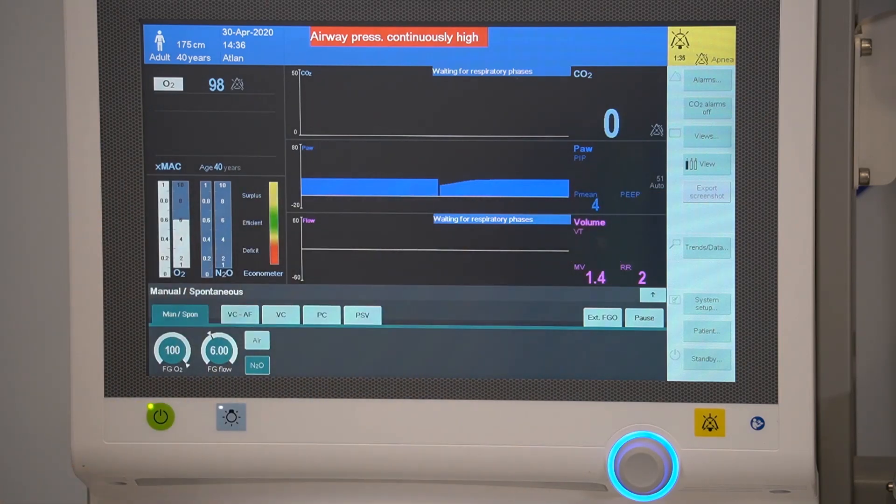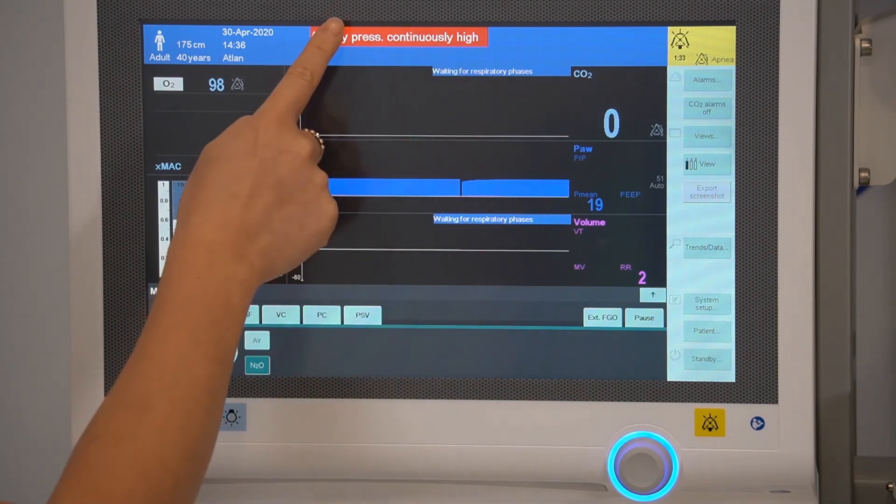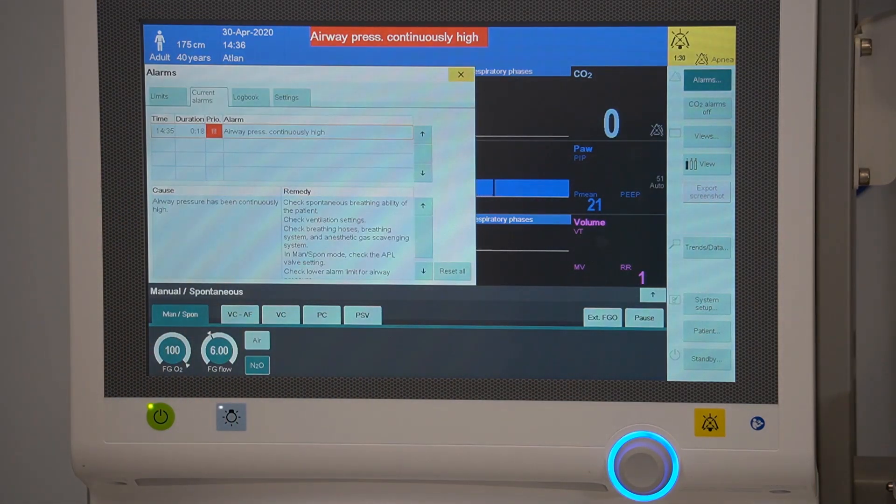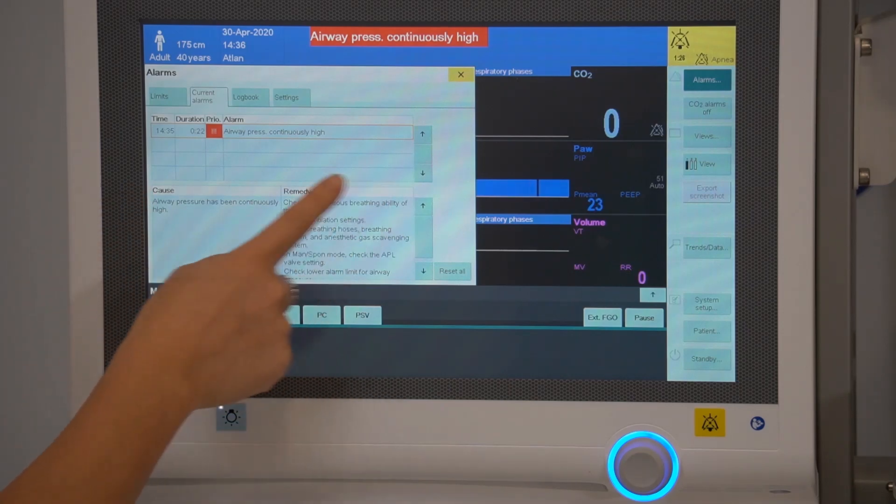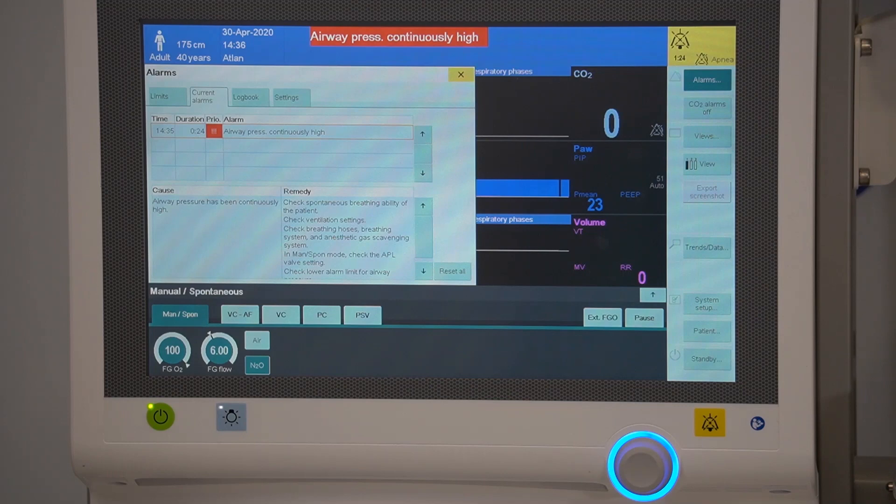To look at current alarms, you can select what is being displayed in the headline. This will give you a cause and a remedy to help troubleshoot the error.